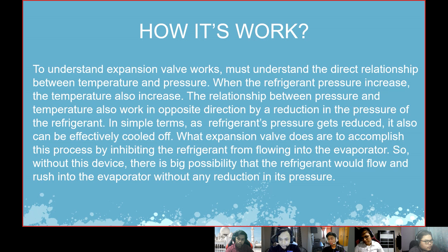Next, there are four types of expansion valve. The first type is the automatic expansion valve. This type uses a pressure actuated diaphragm. It maintains a constant pressure in the evaporator. The setback is that it is not efficient if the load fluctuates, hence this type is not suitable for use in air conditioning, as the load fluctuates a lot during operation.